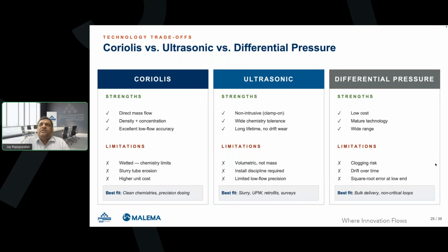In case of differential pressure technology, it's low cost, mature technology, very old technology. It's wide range, but extremely risky in clogging because you're obstructing the flow, and the differential pressure causing element can erode over a period of time. And then since you are using two different pressures for measuring flow, it can lead to drift. And then usually turn down is very low for this technology. You can only measure limited range for each size of the product, so to speak. The typical best fit for this application is bulk delivery, non-critical loops.